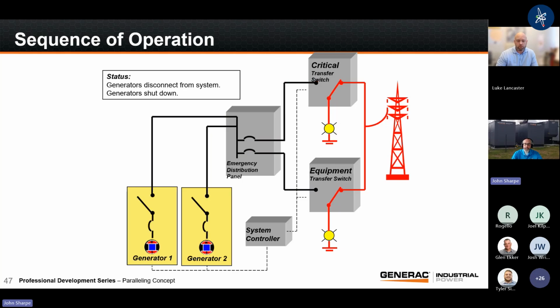So that's a pretty straightforward 2-unit, 2 priority parallel generator system. This would be no different if it was a traditional paralleled versus an integrated paralleling. All of these steps happen. It's just a matter of where they happen.